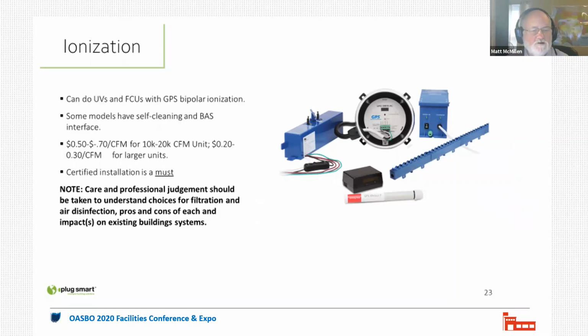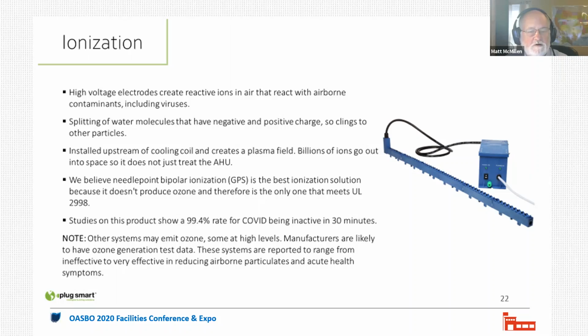One thing on that previous slide I'd note: it's important when selecting ionization systems to look at the ozone emission associated with them. Ozone will accelerate corrosion, and it's also harmful to your health depending on the levels. So it's important to understand both what the manufacturer's data is and what the unit manufacturers, say air handler manufacturers, and health department officials say about safe applicable levels of ozone. That's a key point to look at with these ionization systems.